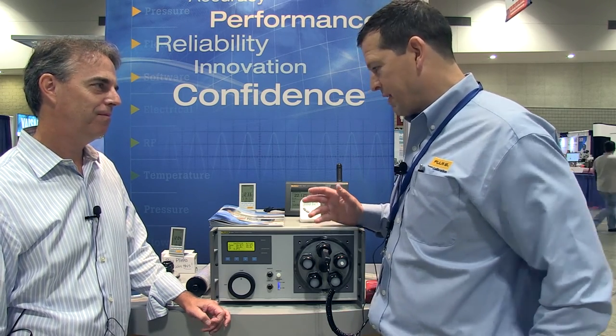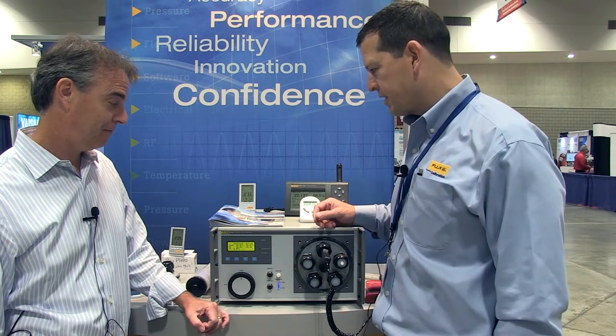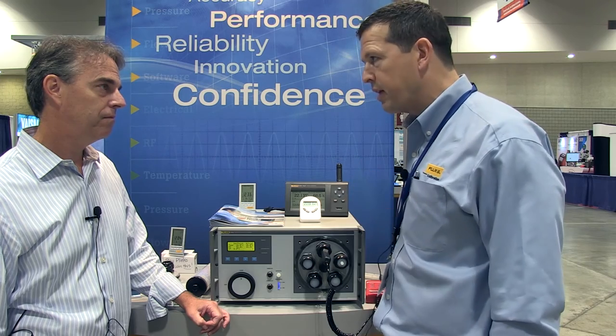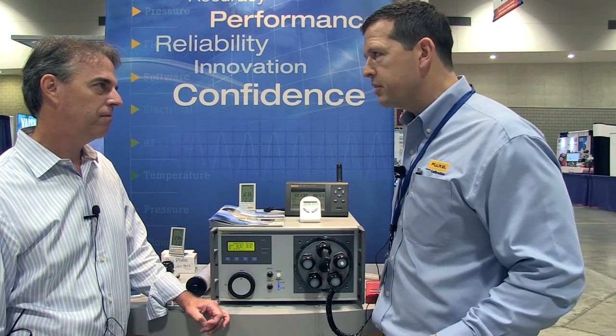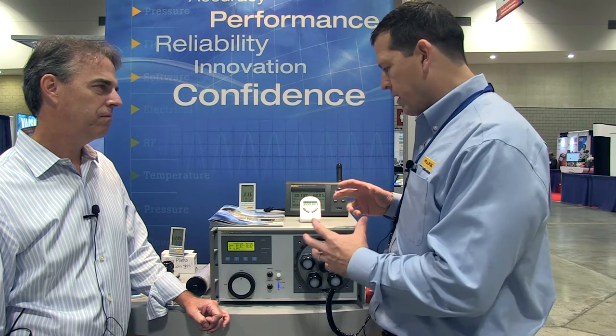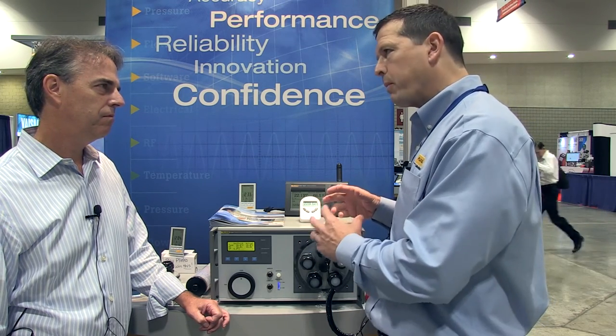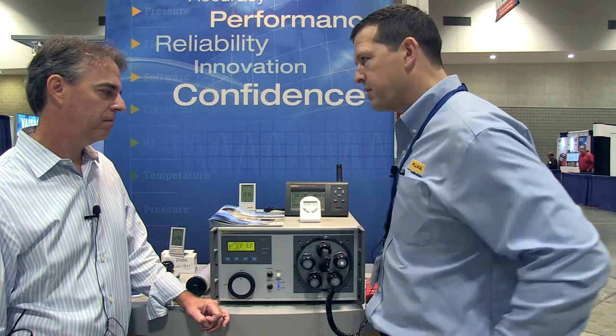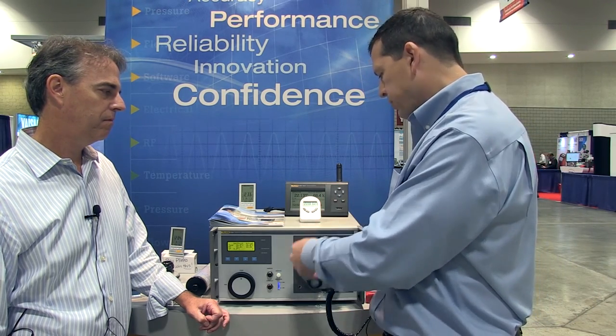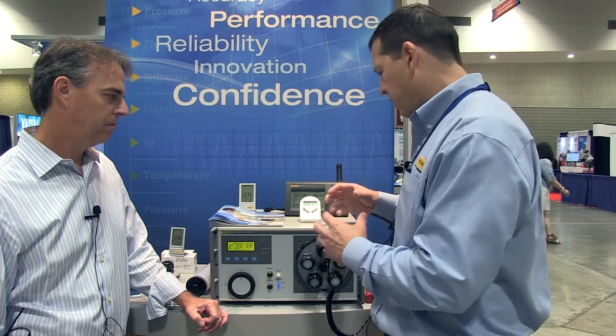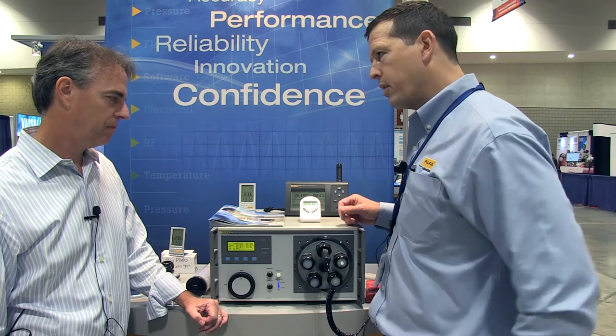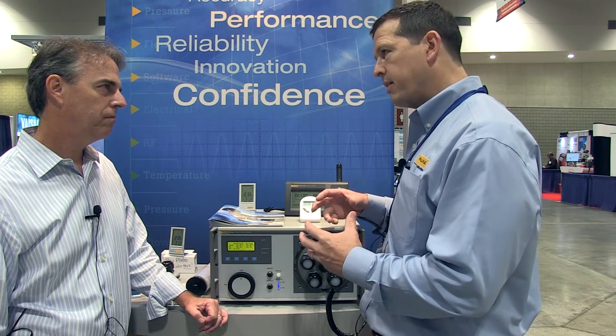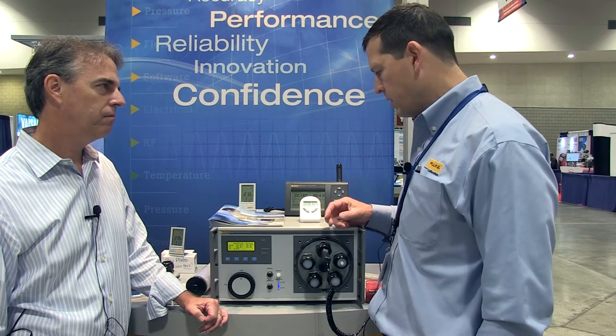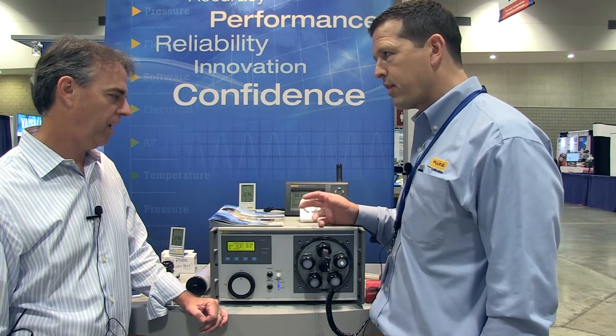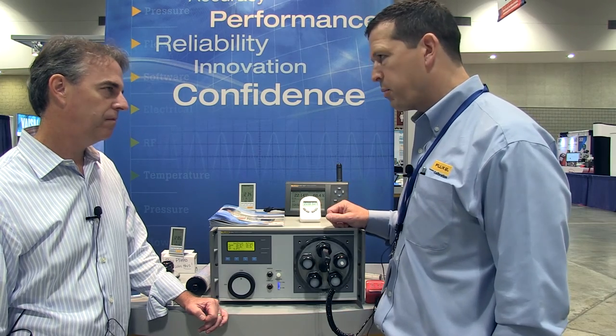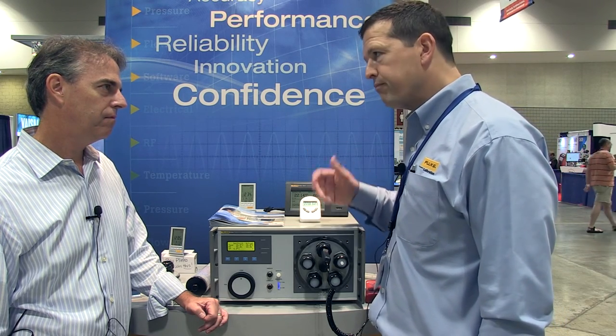A couple other things we wanted to bring to the product to differentiate ourselves is bringing Fluke metrology to industrial humidity calibrations. A lot of times you can't get a good, reliable specification and understanding of the uniformity you have in a chamber, for example. We've done a lot of testing to understand the hole-to-hole uniformity and the uniformity throughout the entire operating cavity, so we have really well-specified humidity and temperature uniformity and stability specifications. We ship each one with an accredited calibration out of the Utah facility, the same facility that made Hart products for many years. That's about it.